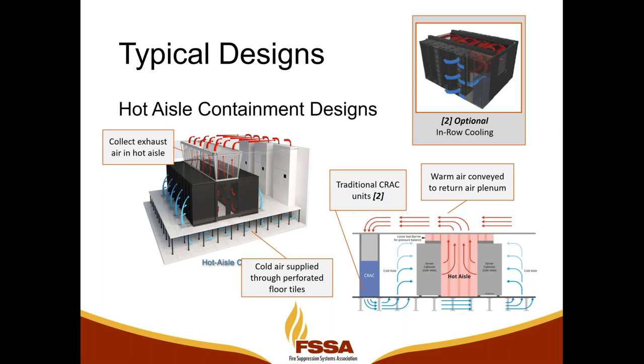One thing that you'll notice between a hot aisle containment data center and a cold aisle containment data center is that hot aisle containment data centers are more comfortable when you walk into them because you're amongst the cooling air. With cold aisle containment, we contain the cold air, so you're actually in the hot aisle outside of the space. So they're much warmer to walk into, which frankly a lot of people don't like.